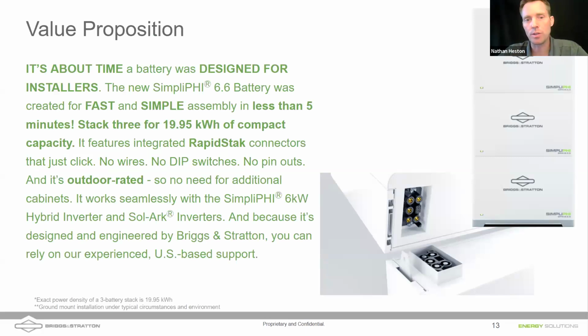There are some advantages, I think, that the SimpliPHI battery has over HomeGrid. One of the notable ones is the fact that we can wall mount these batteries. Another one is this RapidStak technology. We are passing the full communications and the full power through the batteries simply through this stackable connector. So you simply just set the battery modules on top of each other, and all your communications wiring is done through this. I also like the fact that the SimpliPHI 6.6 batteries are outdoor rated.